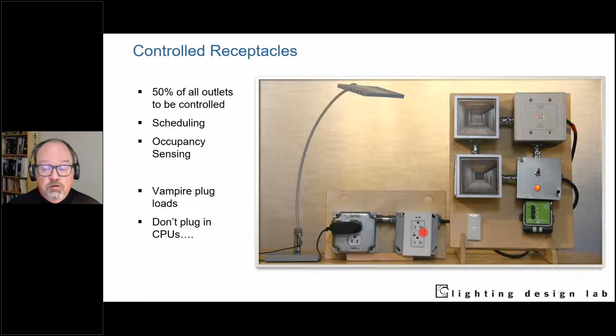So, a quick example. I'll just turn the lights on. Now you'll see the task light in the controlled receptacle going on and off with the switch here. That could be the switch, or it could be an occupancy sensor. This is one way to do it: a smart receptacle with a radio frequency controller built in, taking a signal from the lighting control system's communications hub and switching on and off accordingly. Or it could be a load controller similar to this one—a 1 amp or 3 amp load controller, though you can get 20 amp load controllers too, so the system can turn circuits on and off that way. Some manufacturers offer smart receptacles themselves; others control circuits based on a 20 amp load controller. Either way, it's not terribly difficult.